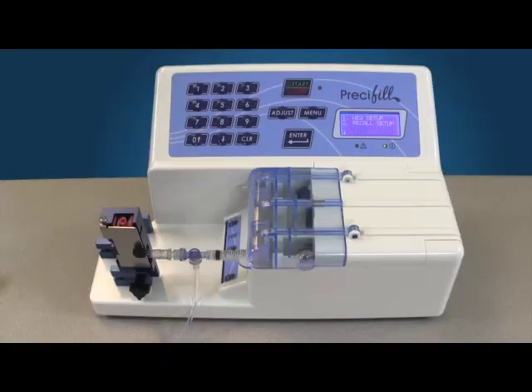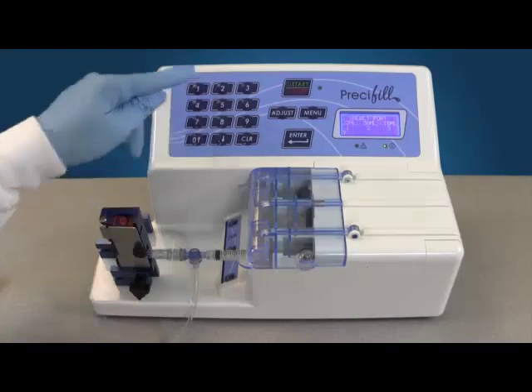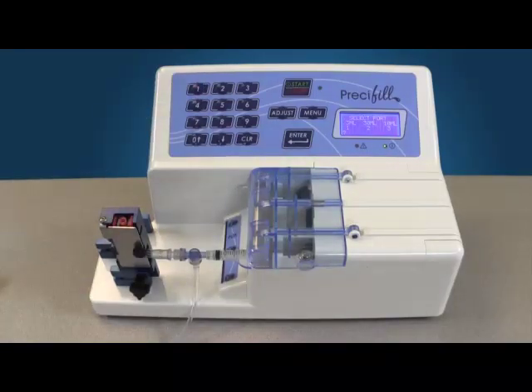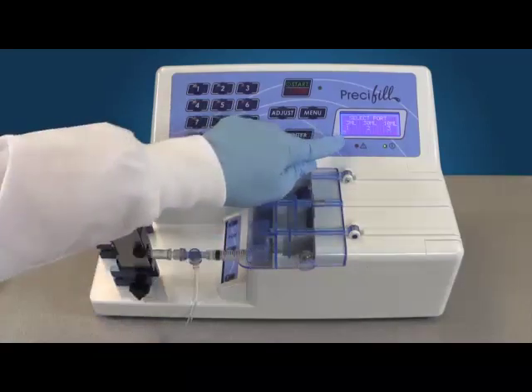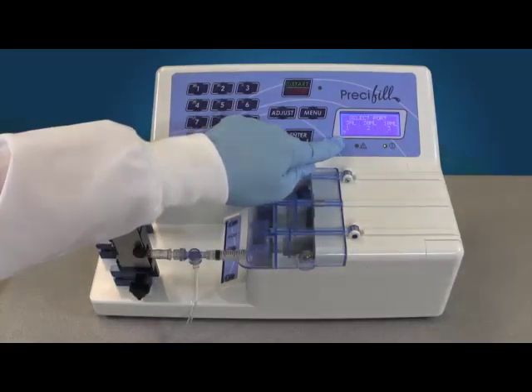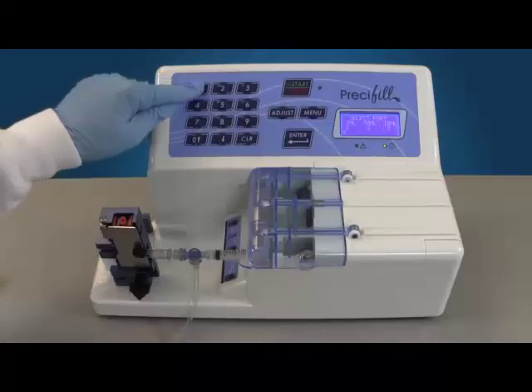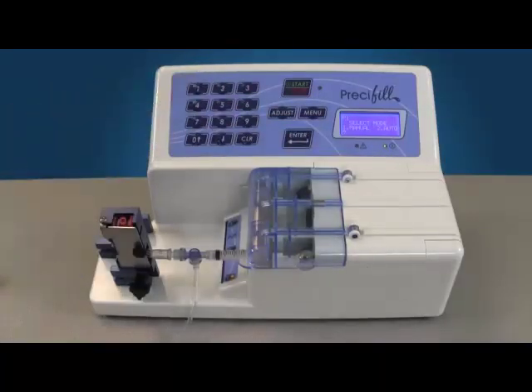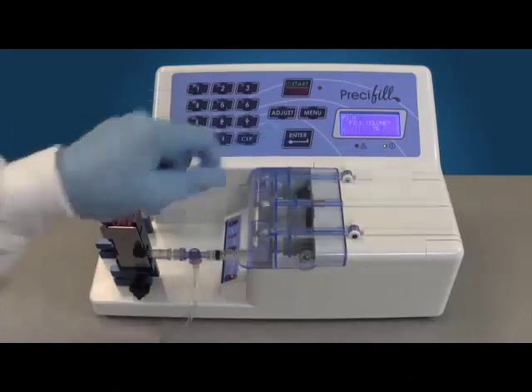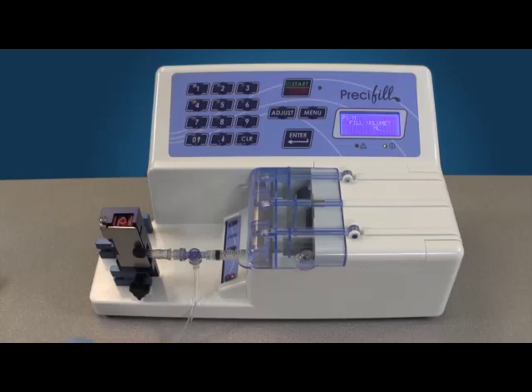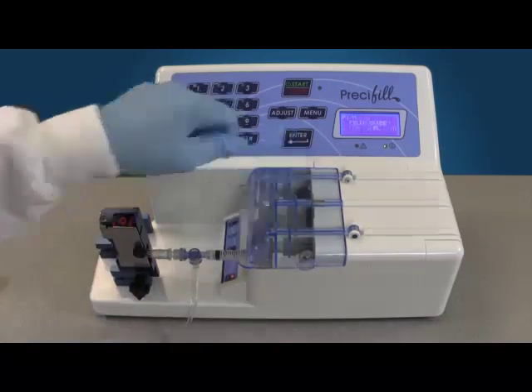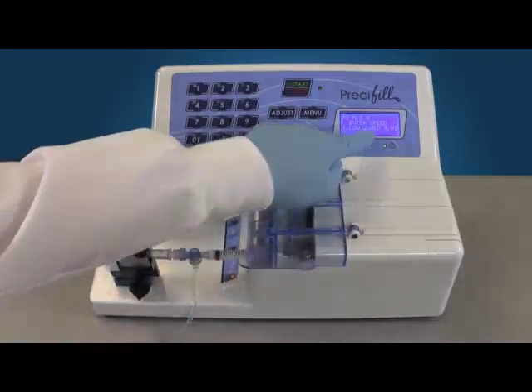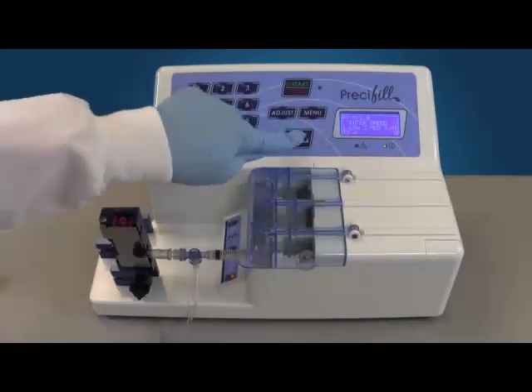To set operating parameters, select number 1 for new setup. Select the port being used. If you are unsure which port to choose, refer to the chart. 1 for 3 ml, 2 for 30 ml, or 3 for 10 ml, and press enter. Select the operating mode, 1 for manual, and enter. Enter the drug volume required in cc and enter. Select the speed, low, medium, or high, and enter.